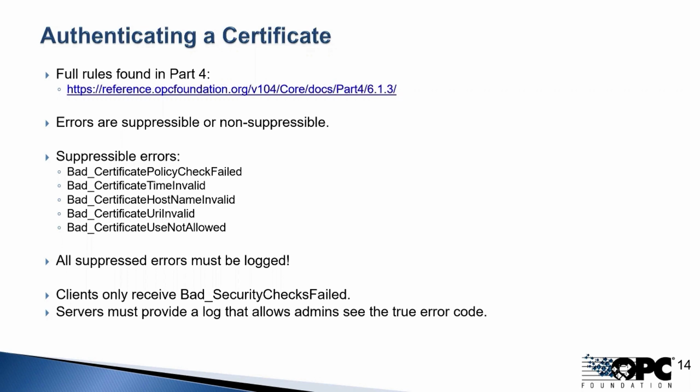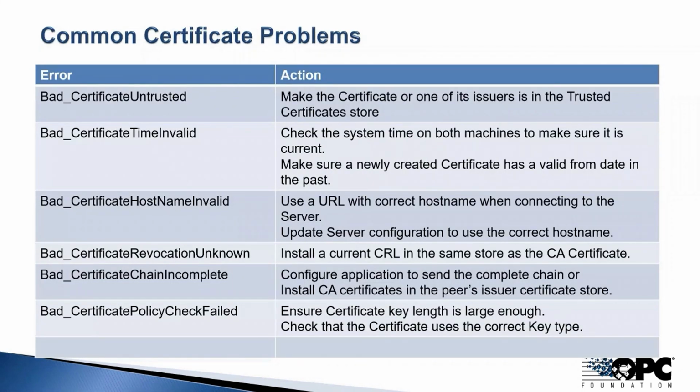And that's why, with any certified product, one of the things that the test lab will look for is that the log is there and it's reasonably accessible to allow people to see the true reason for the failure and make it easier for you to fix it. So here's a few common errors and common resolutions that people run into.